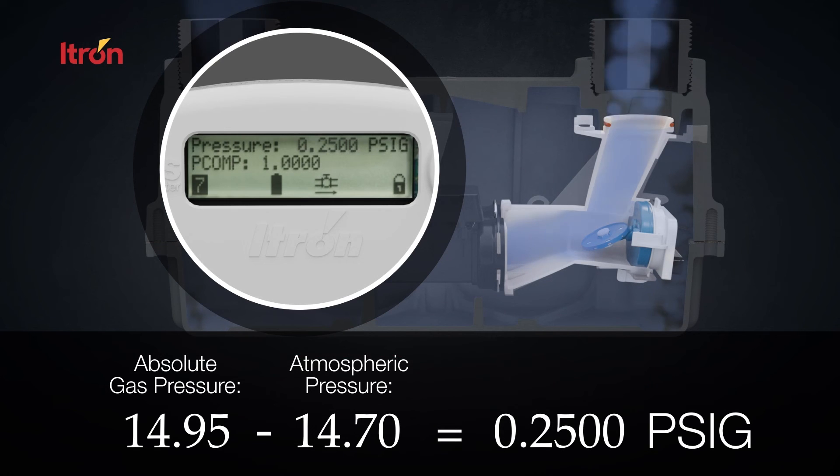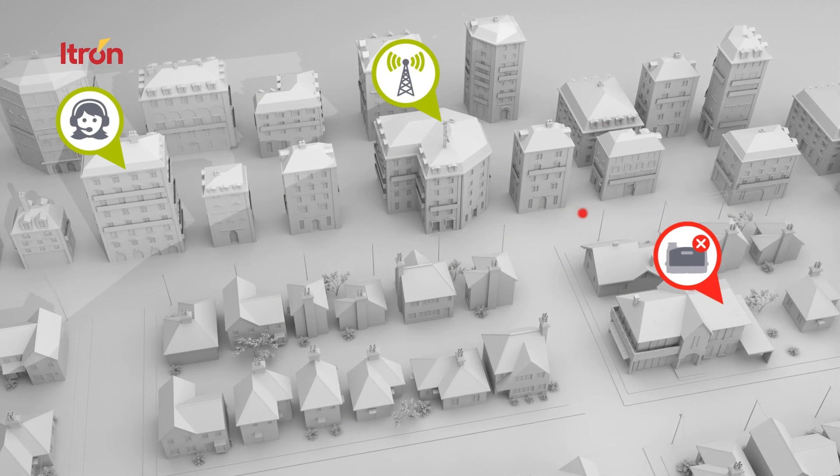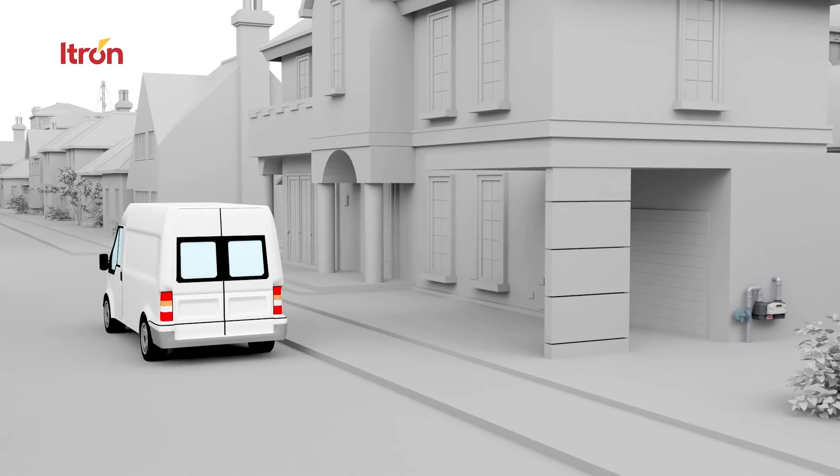The meter calculates the gauge pressure of the gas flowing through the meter. The meter will automatically close the valve, shutting off gas flow once a utility configurable high pressure limit is reached. Additionally, in network mode, as soon as a high pressure or low pressure threshold is reached, an alarm is sent to the head end.